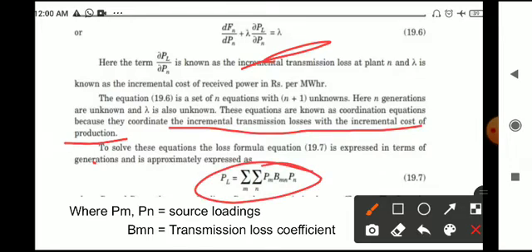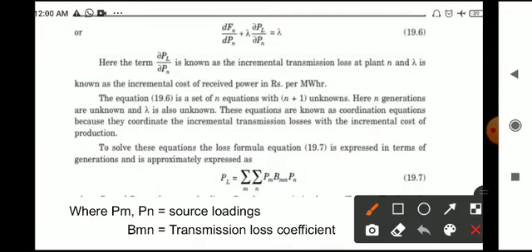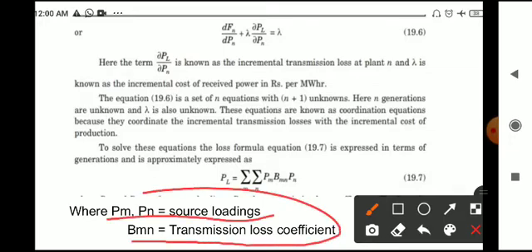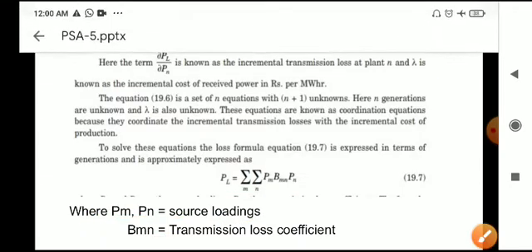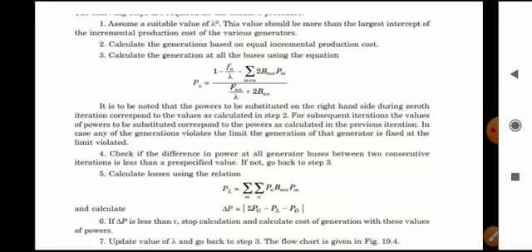To solve these equations, the loss formula is expressed in terms of generations and is approximately given as PL equal to sigma_m sigma_n PM * Bmn * Pn, where PM and Pn are the source loadings and Bmn are the transmission loss coefficients. An iterative method is used to solve these equations.